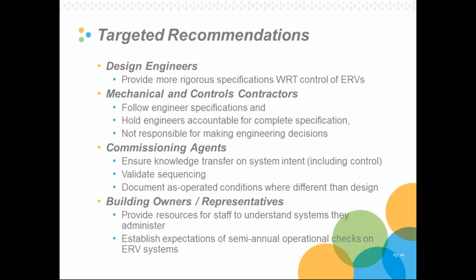Some targeted recommendations. Design engineers would really help a lot if they provided very rigorous specifications, especially with respect to control of ERVs. I'm talking detailed sequences. This reduces a lot of the uncertainty that will happen down the chain. This goes directly into the mechanical and controls contractors. They should be following these specifications. And when they don't exist, they should go back to the engineers and hold them accountable for complete specifications. It's not a mechanical or controls contractor's job to be making engineering decisions in the field. And I know from this project that they're often pressured to do so. But that's an easy way for as-implemented energy recovery to deviate from design intent.